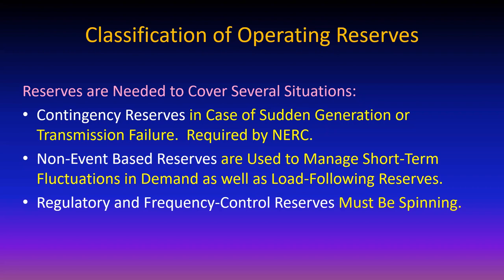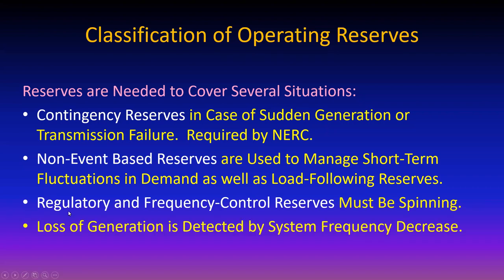But if it's spinning generation, then they need to be spinning so that they don't have to get up to speed - they just need to synchronize in order to give a little extra bump to the production side of the grid. Loss of generation is detected by a system frequency decrease, which is what I just implied in that previous comment.